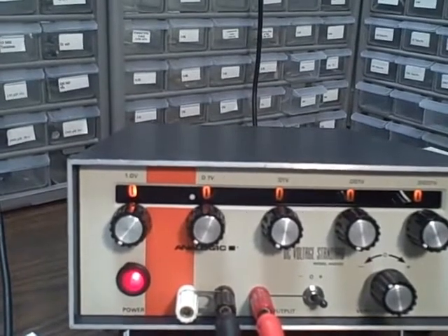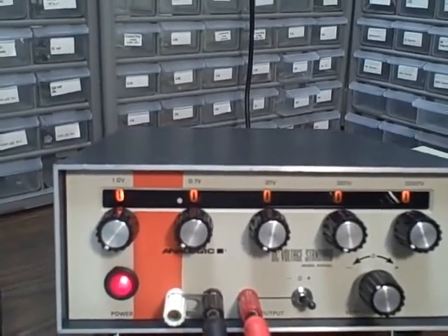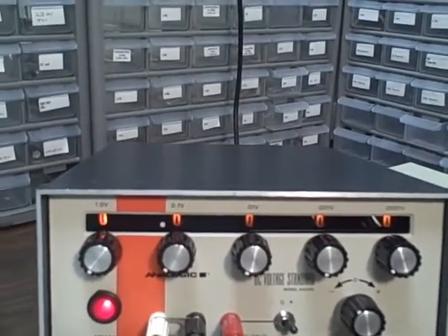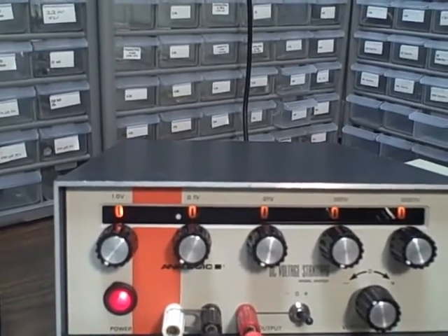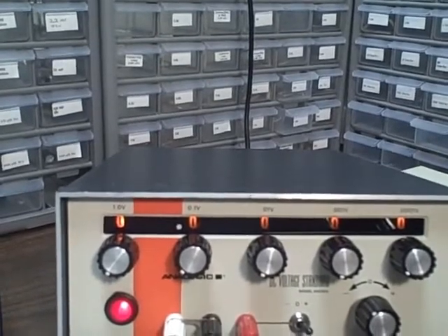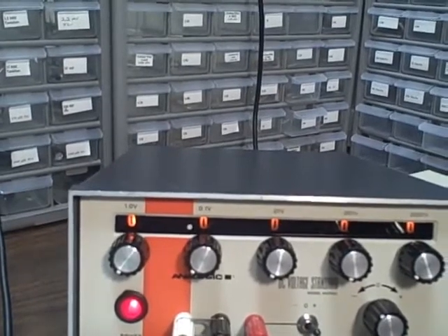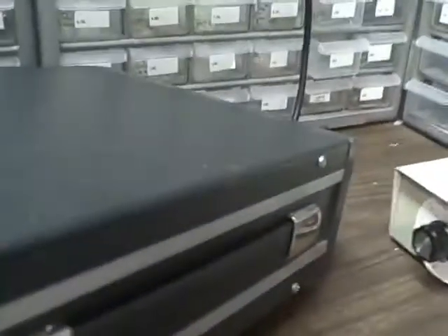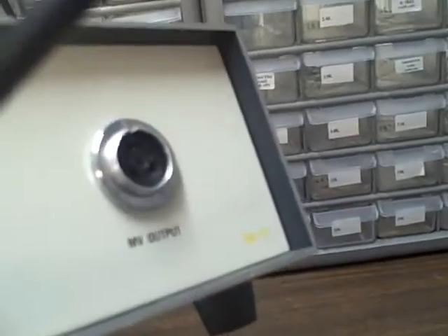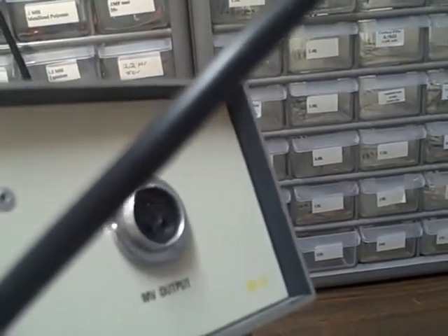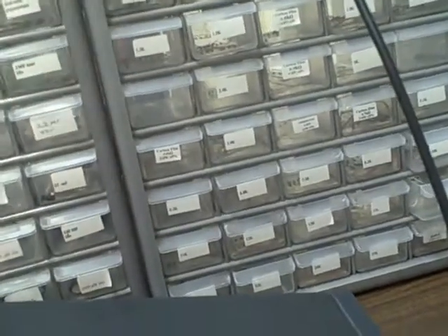One of its hallmarks is that it warms up in about 10 minutes to provide you highly accurate readings. Actually, it's rated readings. And there's only one calibration point in it, one pot that's calibrated for 10.0000 volts when you have a standard attached to it. That's been done. Everything on this, the case is in marvelous shape. There are no major scratches, no major abrasions. It actually looks very new. It also has on its backside a millivolt output. You can output 0 to 11 volts from the front panel. In the back here, it's 0 to 111 millivolts instead of volts, as is on the front panel.